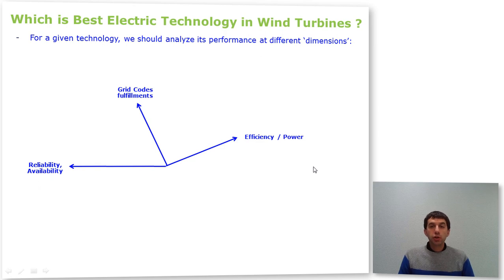Another vector or issue that has to be taken into account is the efficiency, or the power, since both are much interrelated. The bigger the power, from the converter point of view, if we use a full-scale wind turbine, the power electronic converter will be more expensive and more complex. So the double fed induction generator may be in a better position because it's only 30% of that power. However, it depends how much power we're talking about—it's not the same if we're at 8 megawatts, 5 megawatts, or 2 megawatts. The context will be different.